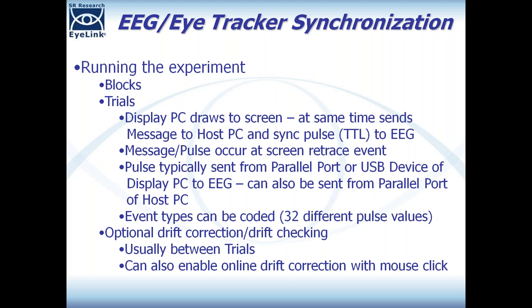On any given trial, the display PC draws the trial stimuli to the screen, and as soon as it does, it sends a message to the host PC for synchronization purposes and a sync pulse to the EEG device simultaneously. Anytime an experimental event happens — presenting an image, playing a sound, waiting for a button press — you want to send markers to the eye tracking data file and to the EEG device basically simultaneously.